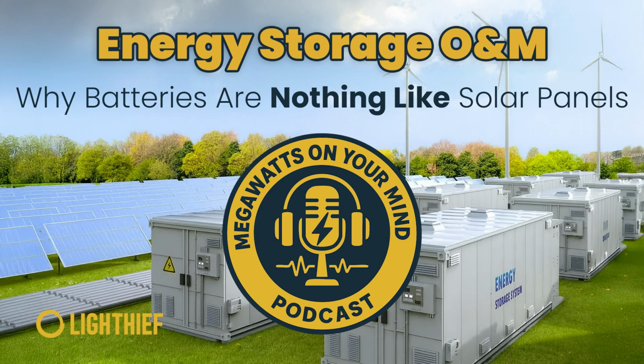Let me be clear from the start. Energy storage O&M is not solar O&M with batteries added on. It's a completely different discipline requiring different skills, different safety protocols, different equipment, and frankly, a different mentality about risk. With a solar farm, if you make a mistake, you might lose some production. Equipment might fail. It's economically painful but rarely dangerous. With battery storage, mistakes can result in thermal runaway, fires, toxic gas releases, and genuine danger to personnel. The stakes are considerably higher.